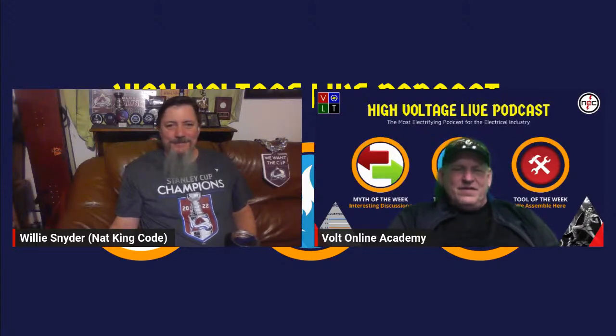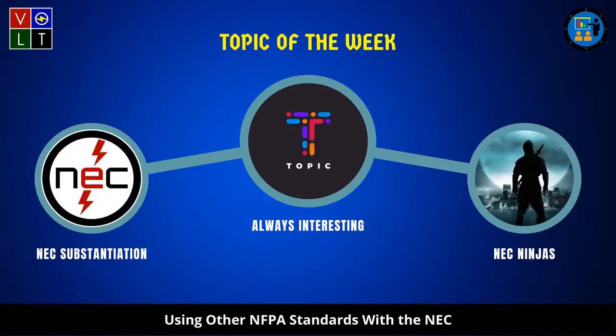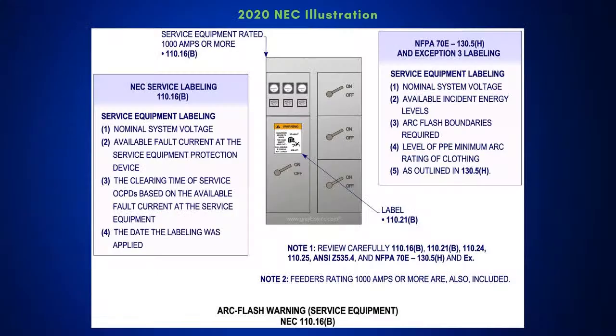All right, let's take a look. Let me show you what I've done here. Now what we're going to look at is using other NFPA standards with the NEC, and this is one of our illustrations. This is 110.16(B), where you get into your arc flash warning. If you look on the left-hand side, what I like to tell people, like if you were in our online course, we would have something laid out like this. In 110.16(B), you could click that section and pull this information up. And it talks about the service labeling.